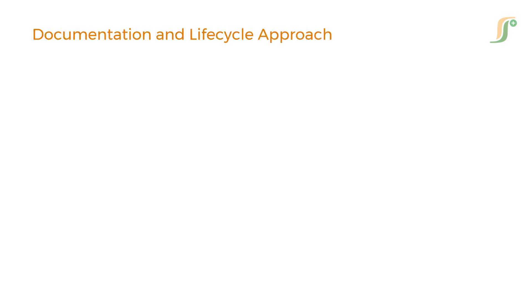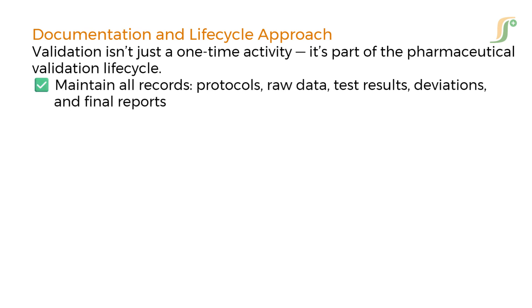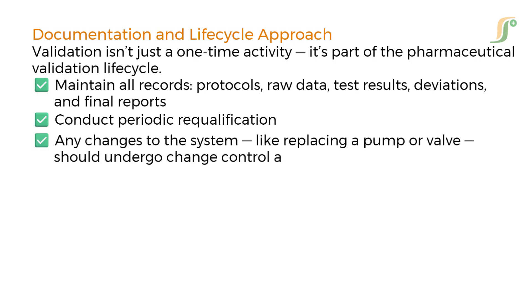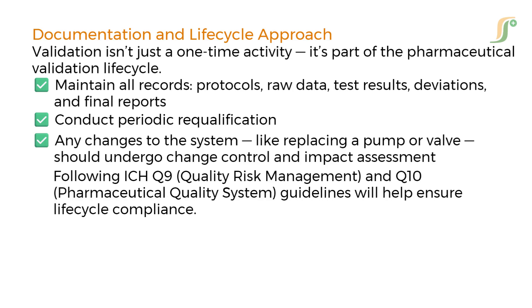Documentation and life cycle approach: validation isn't just a one-time activity — it's part of the pharmaceutical validation life cycle. Maintain all records, protocols, raw data, test results, deviations, and final reports. Conduct periodic requalification. Any changes to the system, like replacing a pump or valve, should undergo change control and impact assessment. Following ICH Q9, Quality Risk Management, and Q10, Pharmaceutical Quality System, guidelines will help ensure life cycle compliance.